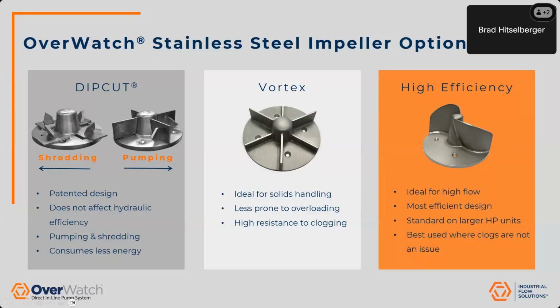Thank you, Brad. Brad did a great job of explaining the dip cut impeller. That is our patented design, which is capable of pumping and shredding when necessary. That is a vortex style impeller. If you have applications where you don't need the potential for shredding, where it's more of a clear water application or rainwater application, we do have a standard vortex style impeller, which still allows the passage of solids, but doesn't have the full functionality of that dip cut impeller.